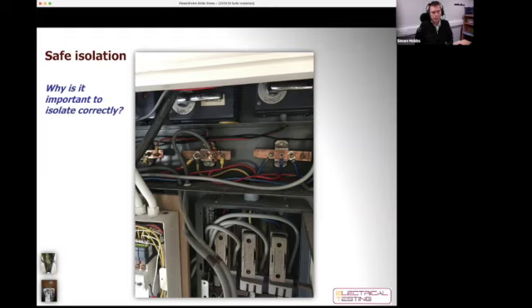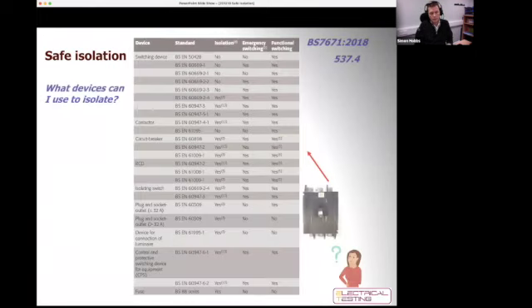So what can I use to isolate my low voltage installation? Again, BS 7671, the wiring regulations, under part 537.4, has a table of devices with all the British Standard numbers that can be used. Generally a circuit breaker will be suitable for on-load switching and isolation, and a disconnector or isolating switch would be suitable for off-load functions.